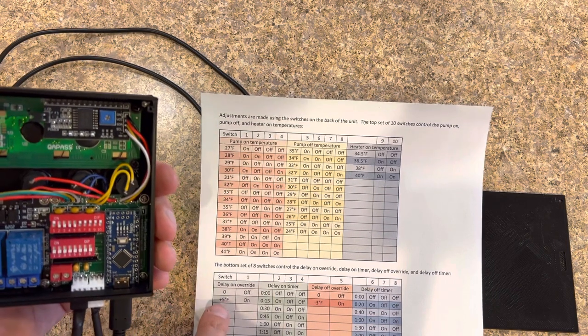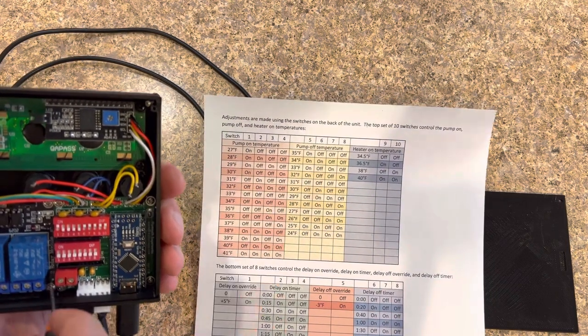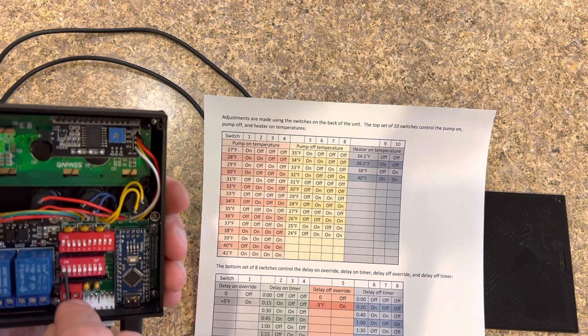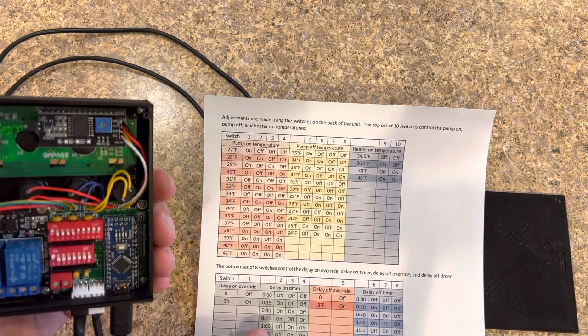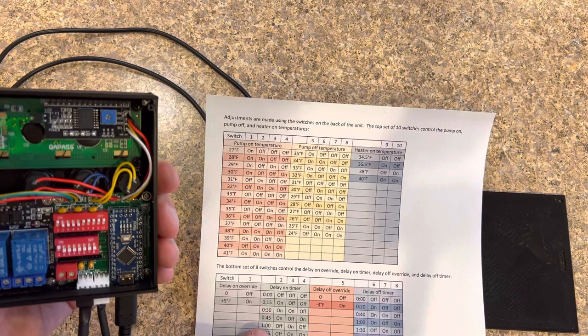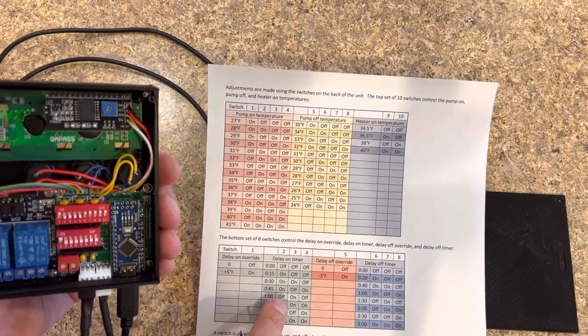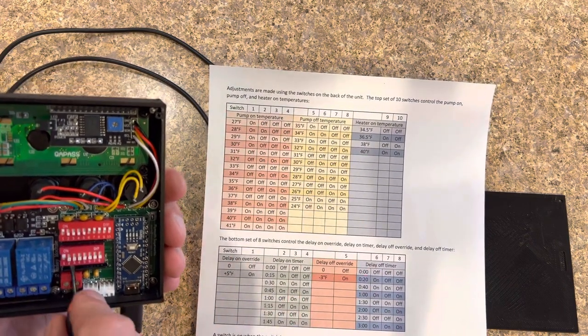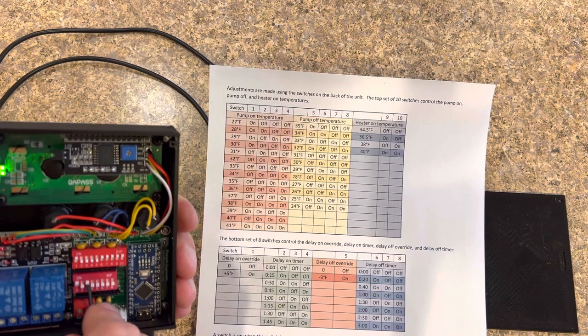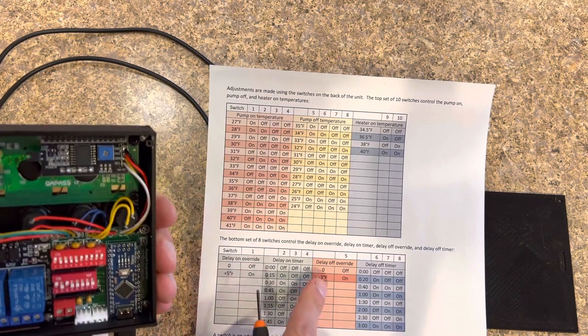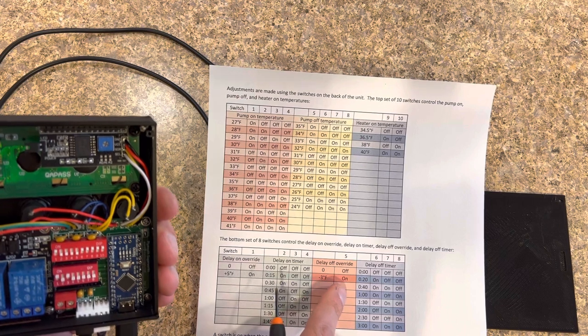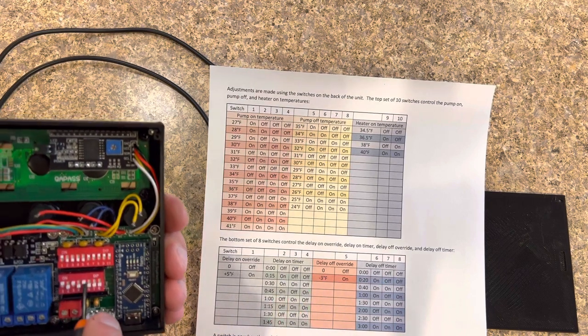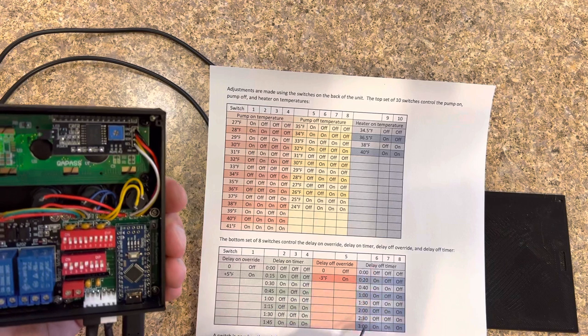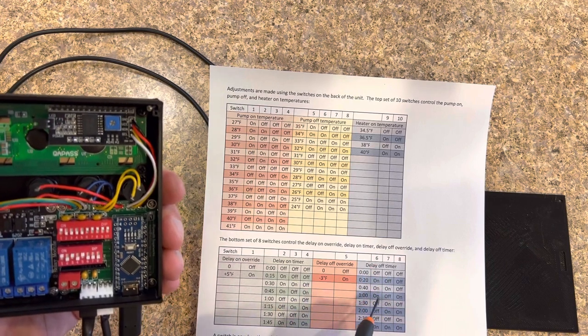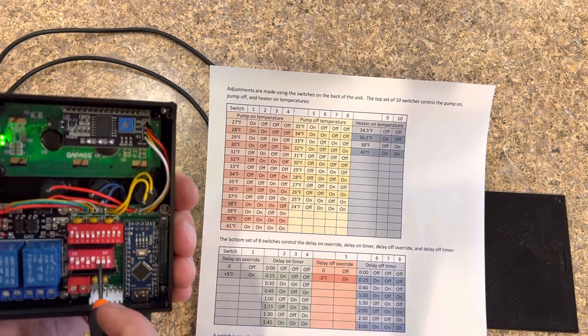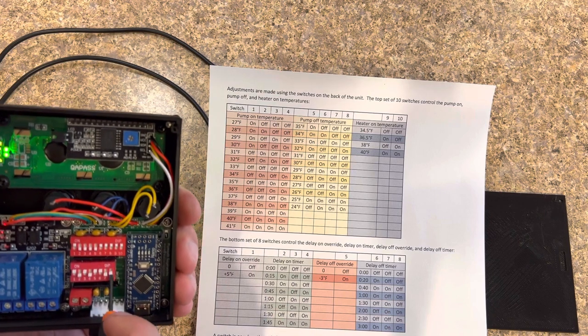And then if we want a delay on override, you can see jumper 1 on this bottom needs to be set. We can do a delay on timer if we wanted it to be 1 hour. That's showing that it should be off, on, off for jumper 2. So off, jumper 3, on, jumper 4, off. We want a delay off override, jumper 5 should be turned on. So we turn that on. And then a delay off timer was set 1 hour. We want on, off, on for these last three jumpers here. So on, off, and on.